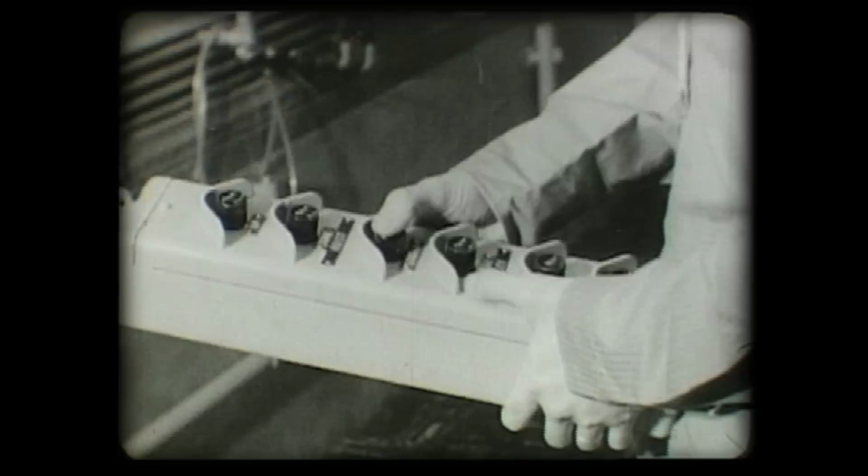This is a special cargo door on the floor of the canyon, not normally used by personnel. The problem of ventilation in the sub-basement room was solved by keeping the canyon under a negative pressure, meaning the air pressure is slightly lower than outside. If there are any leaks around the doors or crevices, the air will rush into the canyon. A separate system brings filtered fresh air in through the ceiling, sweeps it down past the workers and away from the radioactive materials, and out through an elaborate system of air filtering equipment. This design eliminates any possibility of contaminated air getting outside of the canyon itself.